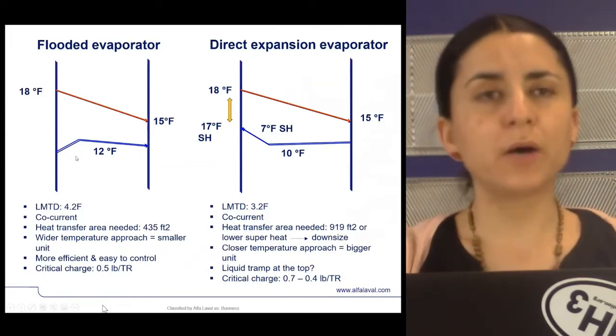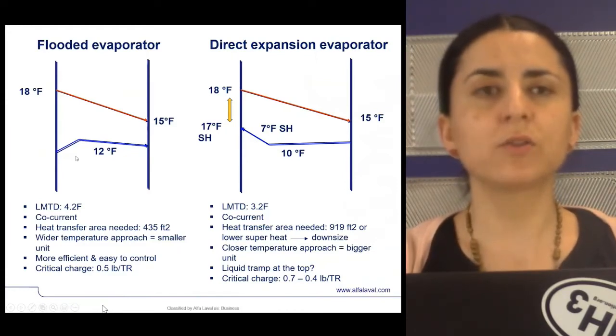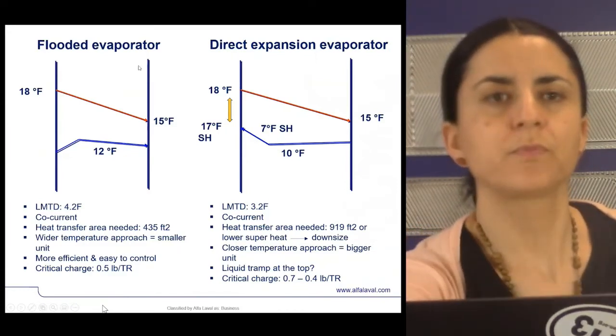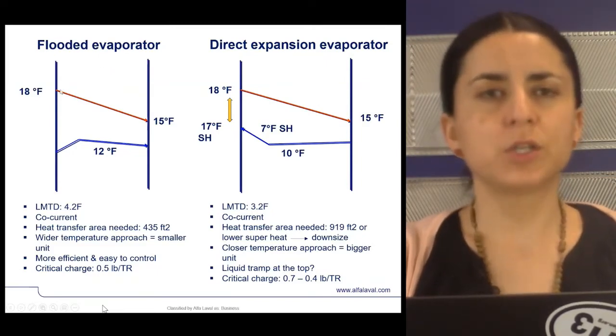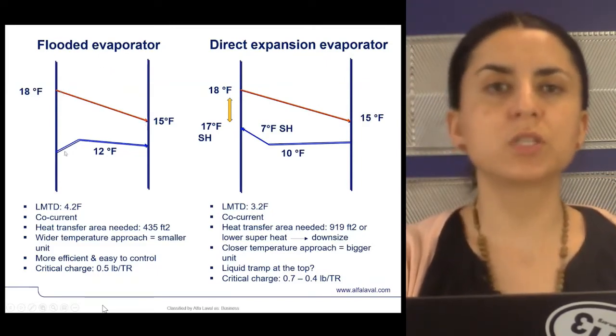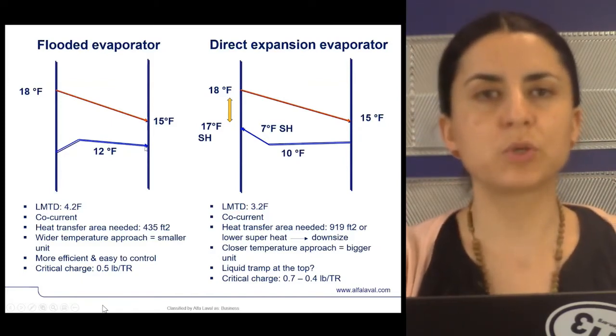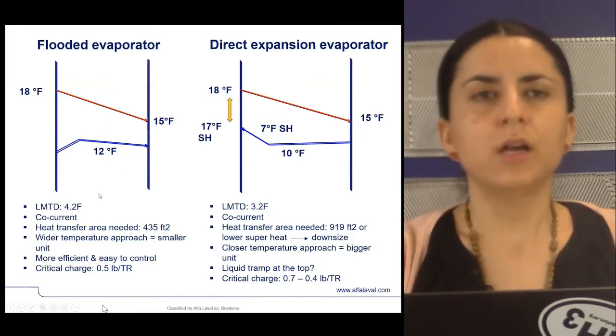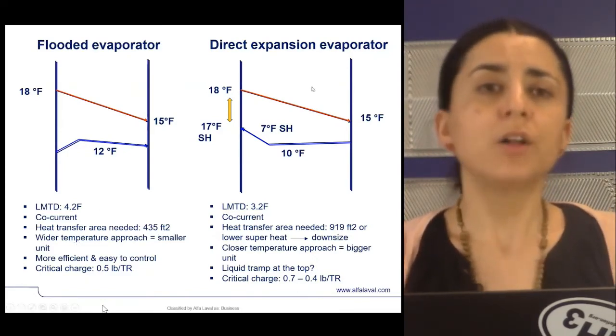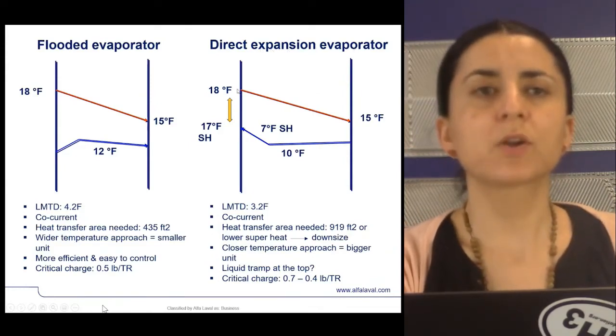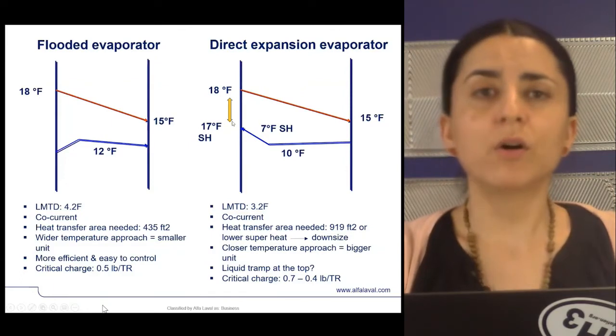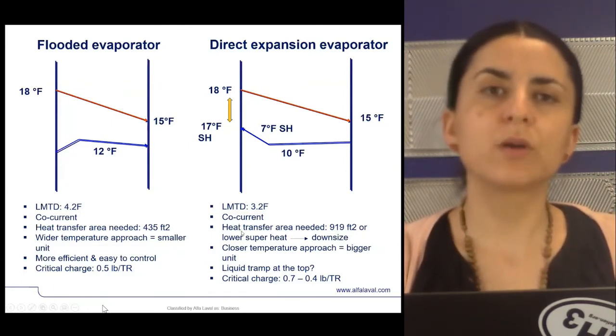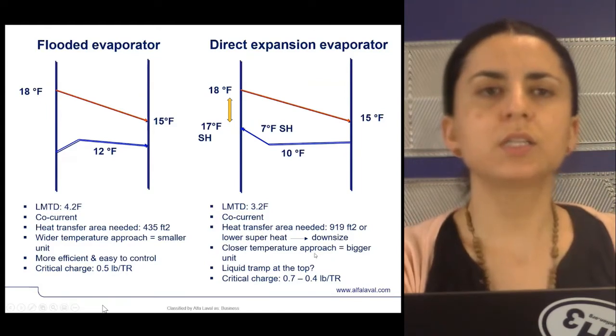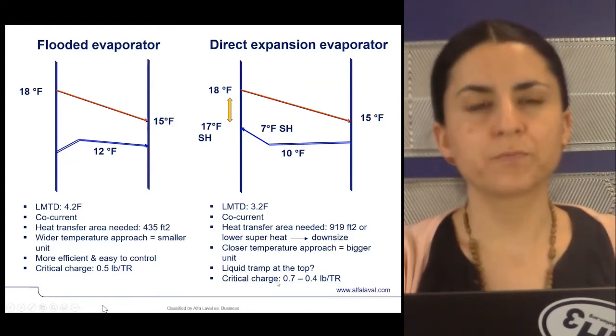Now let's talk about a quick comparison between a flooded evaporator and a direct expansion unit for a typical recreational application. With a flooded chiller, we can have a closer approach between suction temperature and glycol outlet temperature, allowing savings on energy consumption on the compressor by having a high evaporation temperature. On the opposite side, direct expansion requires superheat value in order to guarantee no liquid carryover to the compressor. This superheat leads to a tighter temperature approach.